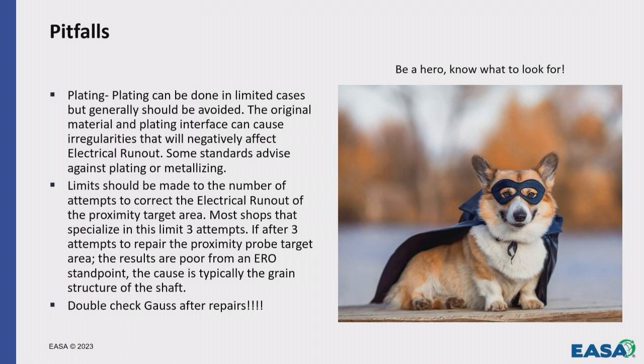Then talking about pitfalls. Plating can be done in limited cases, but it should generally be avoided. So, you know, when we look at what the proximity probes are looking at, they're looking at the grain structure of the steel. So when we metallize or even apply a coating of any type, we typically are going to rough up the surface first and then apply that coating. Well, that proximity probe is going to look through that coating to a certain distance, and it's going to see that rough surface you created underneath the coating, and it's going to pick that up instead of that nice smooth surface you've got on the outside.